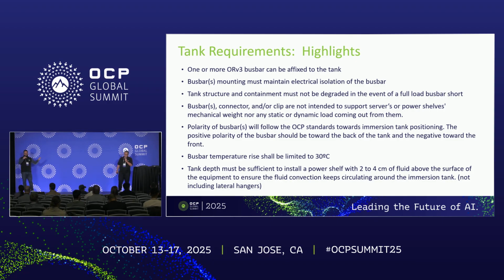As a requirement for the tank, we need one or more busbars in immersion. One benefit of single-phase immersion is that we can run up to 3 busbars in the tank. They're located at the bottom where the fluid is typically pumped, so it's a very cold environment where we can pull more from those busbars. Those are ORV3 busbars, not HPR — with the amount of copper they have, sitting at the bottom of the tank, we can go like 2 or 3 times the kilowatts that the busbar can hold in air in a normal air rack.